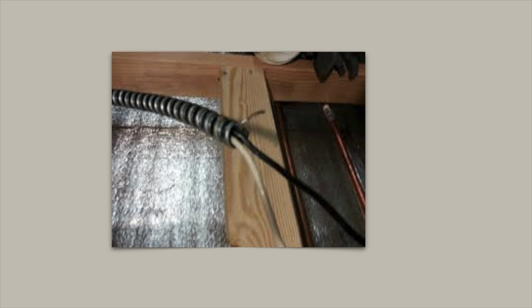BX cable was developed for residential wiring purposes in 1899. It was replaced by Romex or NM non-metallic sheathed cable in 1926 because Romex was easier for homeowners to use. The armored-clad sheathing around BX makes it hard for homeowners to install and rewire. There are no issues with BX. The only reason we need to be aware of it is in verifying aluminum wire. Aluminum wire was never used in the era of BX.